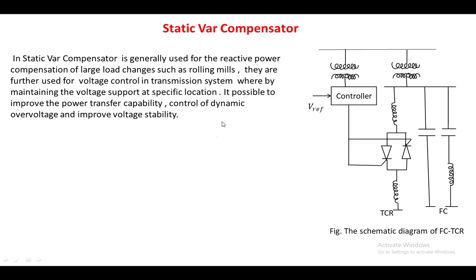The SVC can supply reactive power to the HVDC system during large load variations such as rolling mills. It can also improve the voltage at any point in a transmission system to avoid voltage instability, improve the power transfer capacity of a line, and control dynamic power, voltage, and improve system stability.